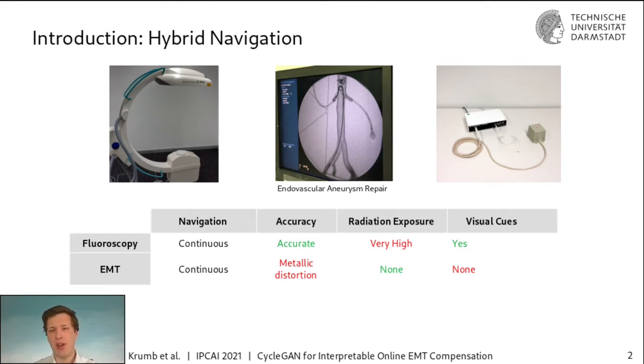Opposed to that, there are technologies such as electromagnetic tracking, or EMT for short. EMT also provides continuous navigation, but opposed to fluoroscopic X-ray imaging, does not expose the patient or the surgeon to dangerous ionizing radiation. However, EMT does not provide any visual cues, and its accuracy can be degraded by metallic or magnetic objects in the vicinity of the tracker.